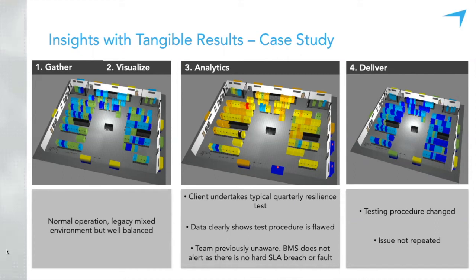As it turns out, in this case it's a customer site where associated with this quarterly event was also a generator test that had been going on. Later analysis of the issue found the BMS had a loop into 3 of the units that stood down in the event of a power outage - a legacy piece of configuration that had been forgotten about, but was quickly removed once it was seen in the software.